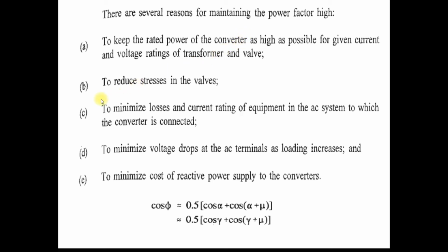The second reason to maintain the high power factor is to reduce the stress in the valves. If the power factor is low, then more current flows into the valves in the high loading condition. Due to that, high stresses happen in the valves. So to reduce the stress in the valves, the power factor must be as high as possible.